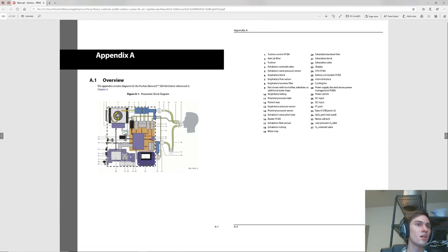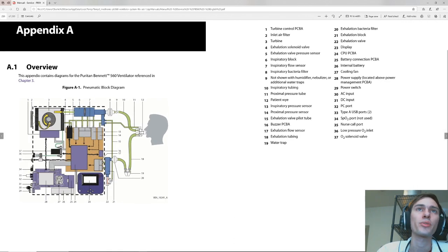Let's see. Pneumatic block diagram. This is where I should have started right here. Let's see if we can zoom in on this. Okay, so we've got 3, which is the turbine. 4 is what we think is the exhalation solenoid valve, which we agree with. All right, and that's wired up exactly the way we think it is. So this is going to be the exhalation pressure transducer, 5. Yep, that's right. So then this DP sensor here is 7. What is that? That's the inspiratory flow sensor. Okay, so whoever was thinking that's a flow sensor is right.